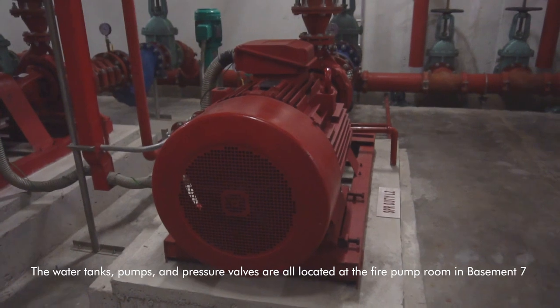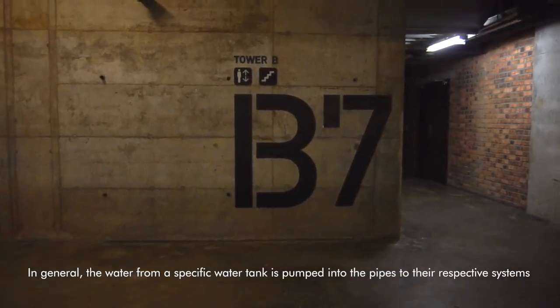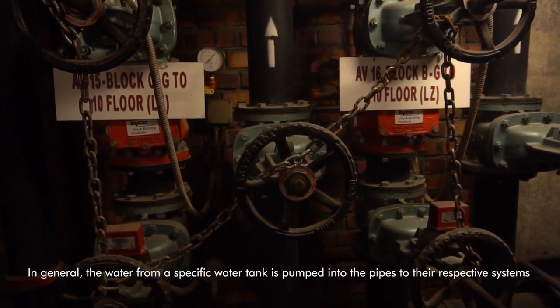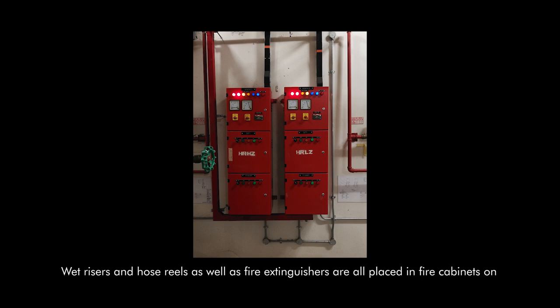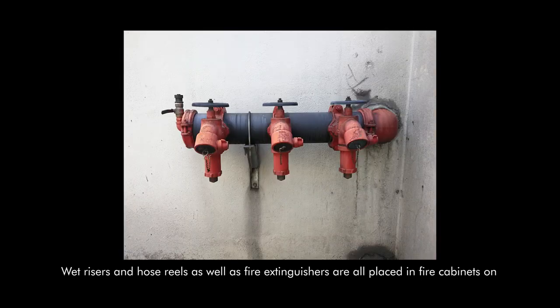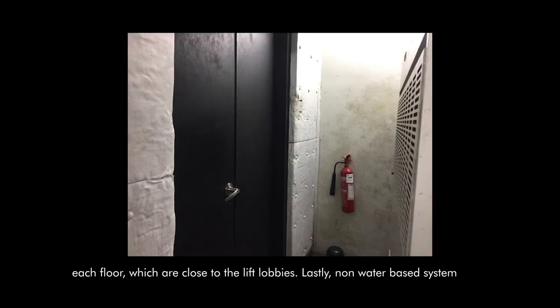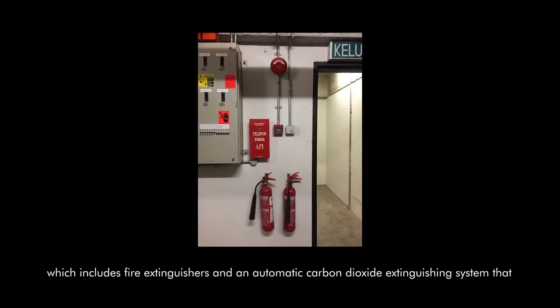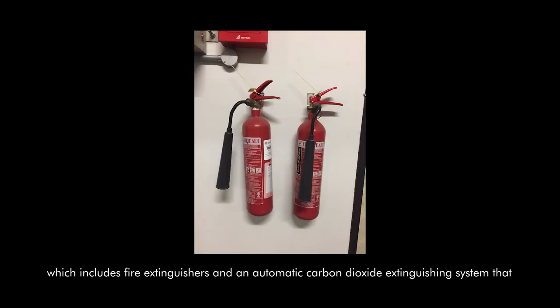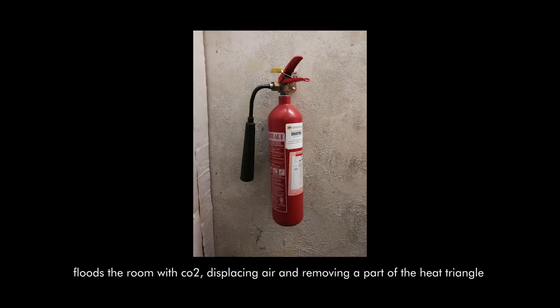The water tank, pumps, and pressure valves are all located at the fire pump room in Basement 7. In general, the water from a specific water tank is pumped into the pipes to their respective systems. Wet risers, hose reels, and fire extinguishers are all housed in fire cabinets on each floor, close to the lift lobbies. Lastly, non-water-based systems include fire extinguishers and an automatic carbon dioxide extinguishing system that floods the room with CO2, displacing air and removing part of the fire triangle.